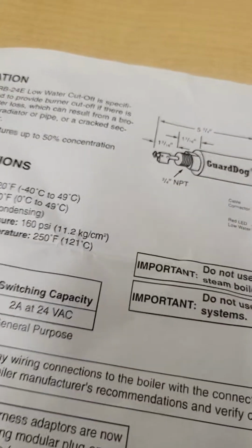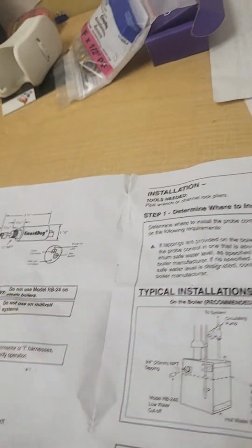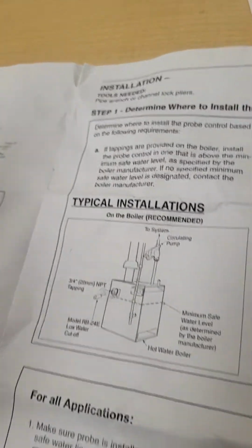This T and an aquastat are two totally different things. The aquastat has a well in it, so you don't have to drain the boiler down for that, but you do have to drain the boiler down to replace a low water cutoff. If you don't know that, you're probably going to learn the hard way. That's the best way I can explain it.